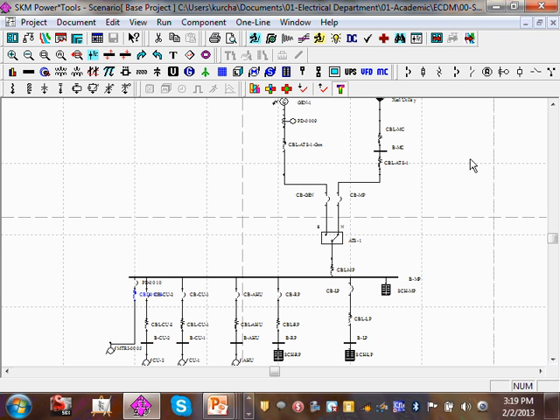Because when we did the analysis, when we did hospitals, before we even bought the system, I would pick up Square D or Cutler-Hammer circuit breakers and run my study with Cutler-Hammer for the worst scenario. When we get the equipment, like you said, we know who the manufacturer is. It will literally take me one-tenth of the time to flip the circuit breaker type to this manufacturer and rerun the system. Everything is set. So really, there are defaults.